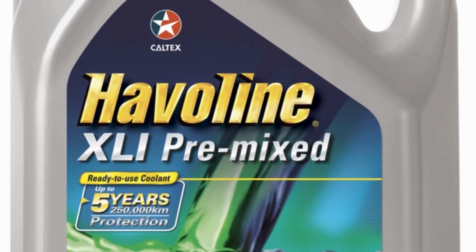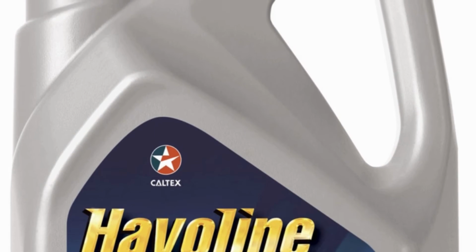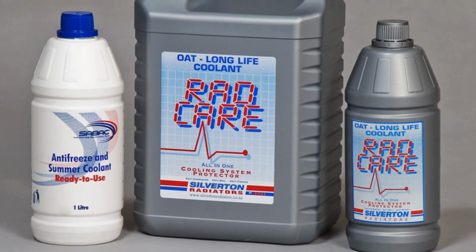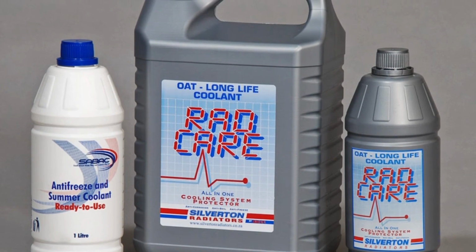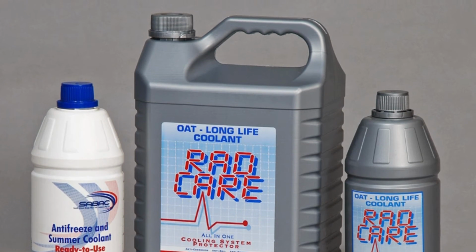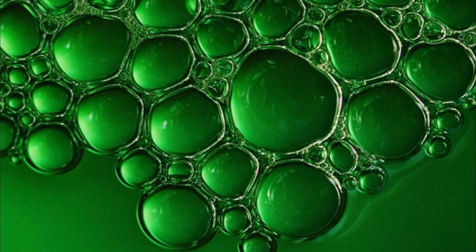The two main glycols that are used as engine coolants are ethylene glycol and propylene glycol. Both can be used in automotive or heavy-duty engine coolants or glycol-based heat transfer fluids, although it is generally accepted that ethylene glycol-based fluids, when used as directed, offer the greatest cost-effective performance advantage. Propylene glycol-based engine coolants or low-temperature heat transfer fluids tend to be used in locations where a low-toxicity product is required, and due to the toxicity of ethylene glycol that cannot be used.